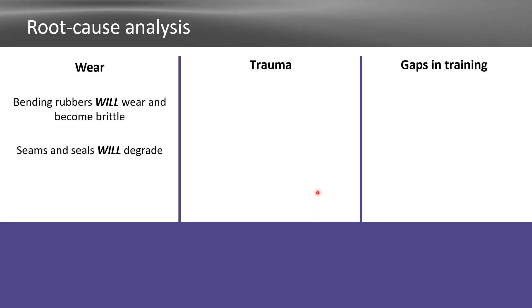We also see people using the proper chemicals improperly. The manual may say, yes, you can use isopropyl alcohol, but what it also states is you can only use that on the control housing, and people may use that on the insertion tube and the tip and the bending rubber and so on. Or they may use the proper chemical on the proper location of the probe, but for an improper period of time, which can degrade the probes even faster.